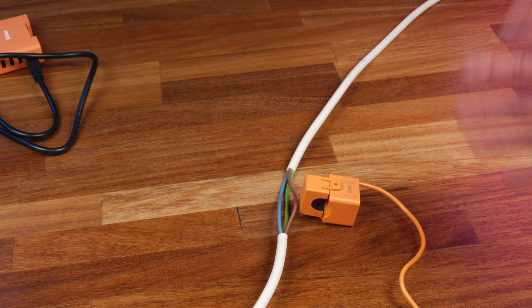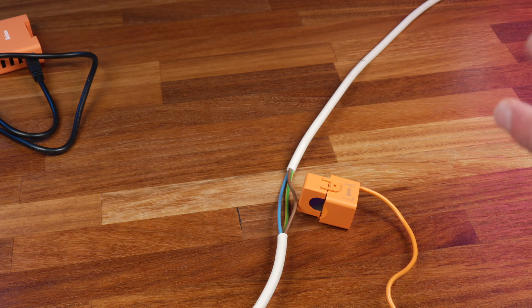If you install this the wrong way round, what will happen is the energy meter will read negative values for the power and the power factor, and with this particular meter, it will track those negative values as production or generation instead of consumption. So what that means is if, like me, you have some sort of solar generation or battery storage, if you have the CT around your grid connection and you're importing from the grid, you'll get a positive value for power, and that will be tracked as consumption, and then if you start exporting power to the grid, your power value will turn negative and it will track that as production.